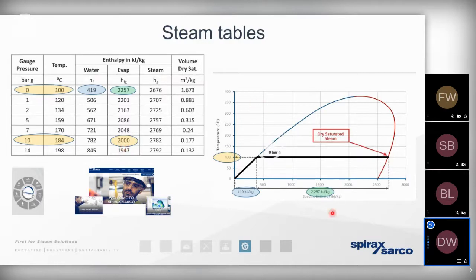So moving across to the temperature enthalpy curve, this really demonstrates the journey that water takes as it evaporates to produce steam. And we're using the example of 0 bar gauge here, where we know water boils at 100 degrees. So if we move the line across horizontally, you can see it's only when we've added that 419 kilojoules of sensible heat that water is going to boil, and that's when we can say the evaporation process starts. Steam starts to be produced. But it's only when we've added the full enthalpy of evaporation or latent heat that we can say the evaporation process will have ended, and we've now got a mass of steam that is fully dry and fully saturated.